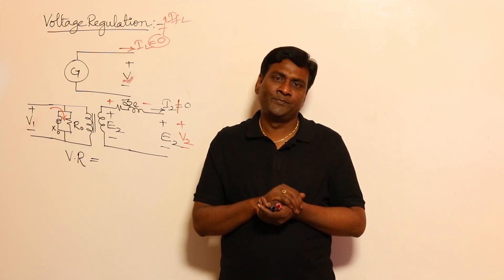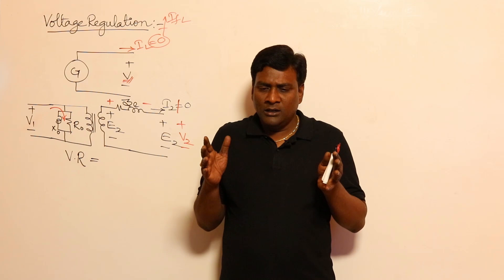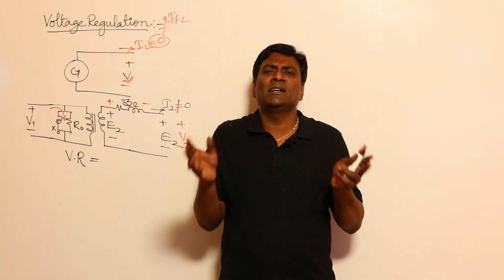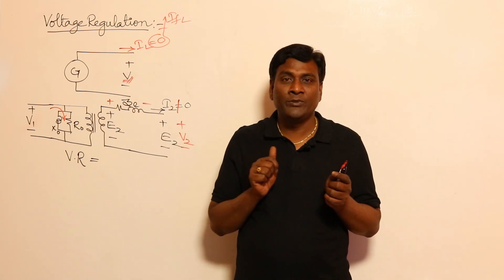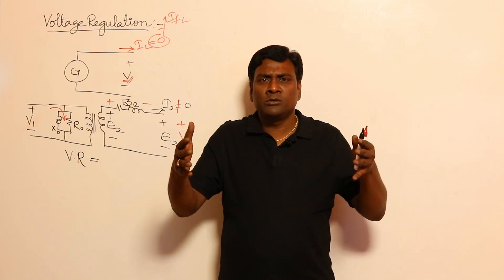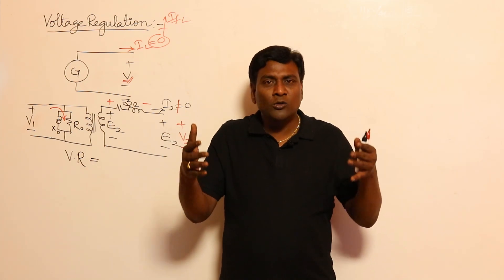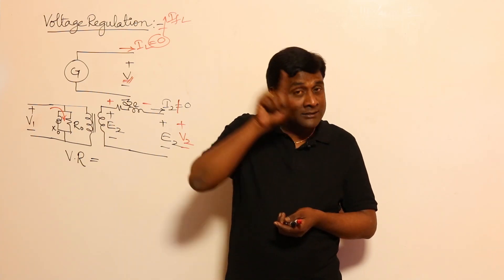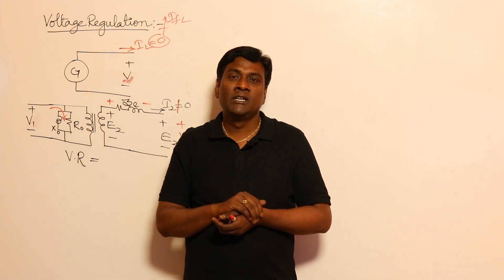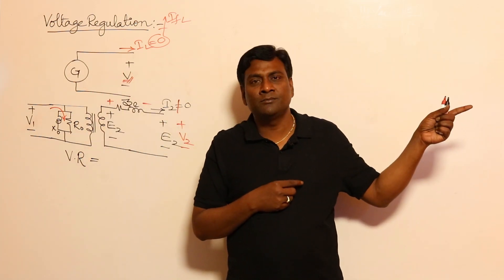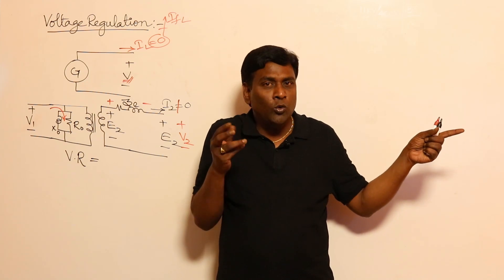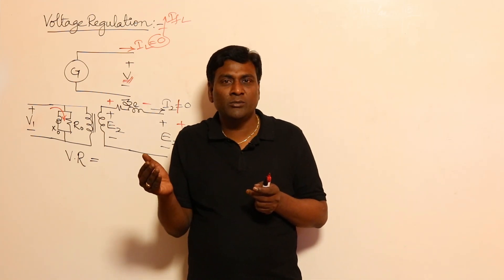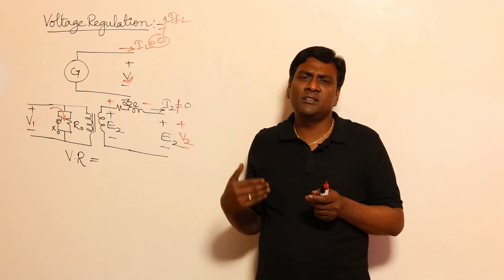For a power transformer, the diversification factor and catchment area are much larger. For your entire hometown, one big power transformer serves the total power demand. If you switch off your AC, somebody may switch on a motor; if that motor switches off, an industry might start. Because of this, load variations are very small in a power transformer. In contrast, load variations are high in a distribution transformer. Power transformers almost always operate at full load.